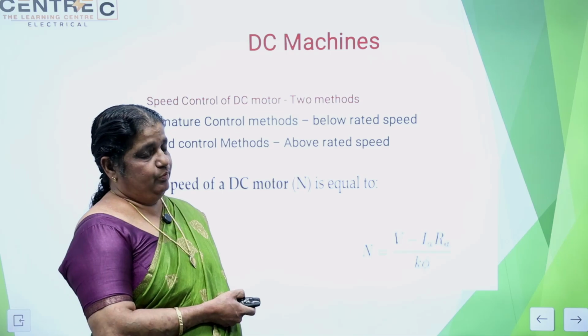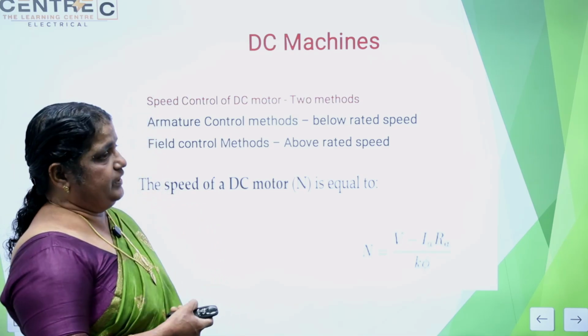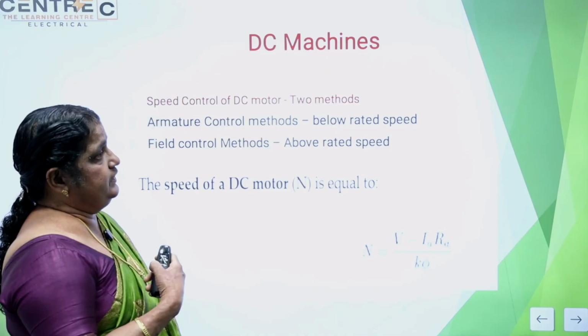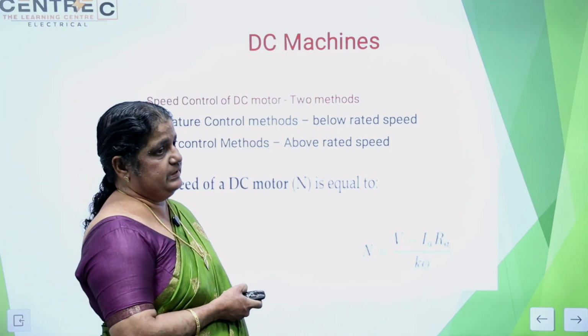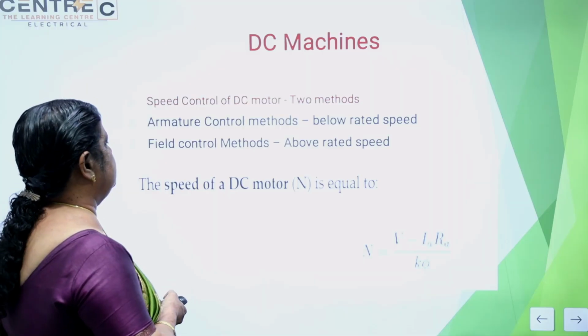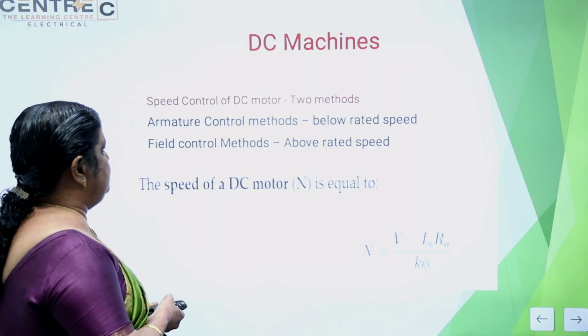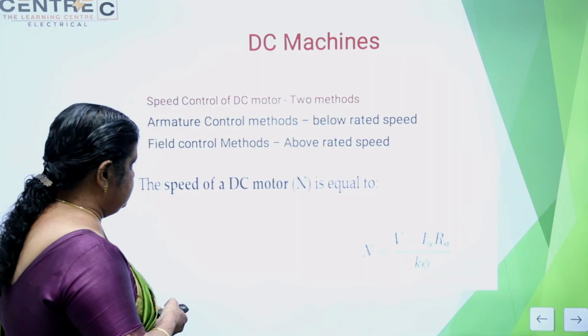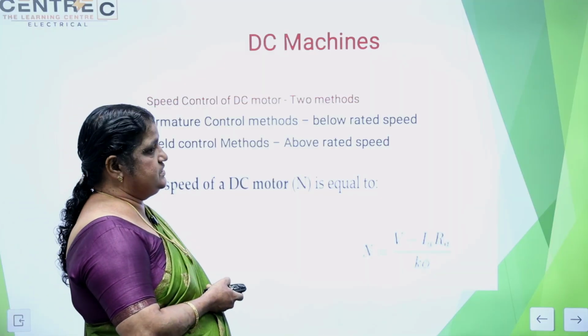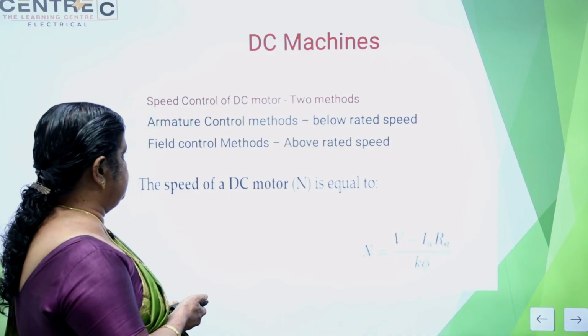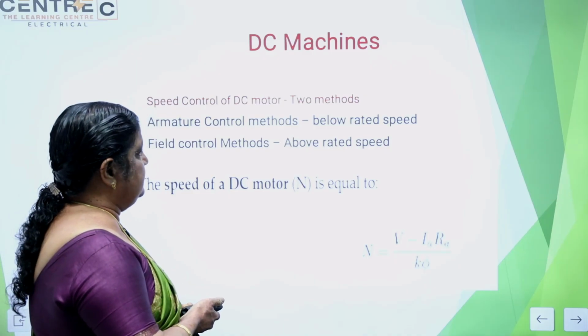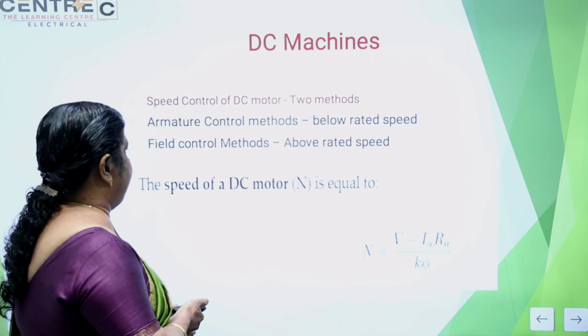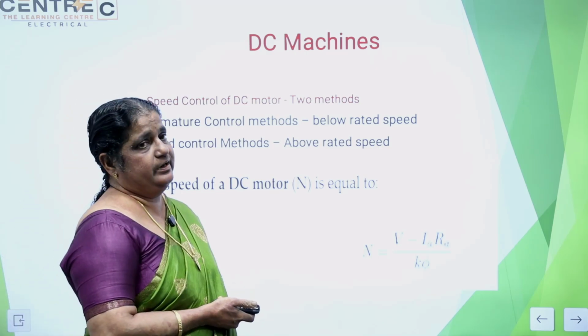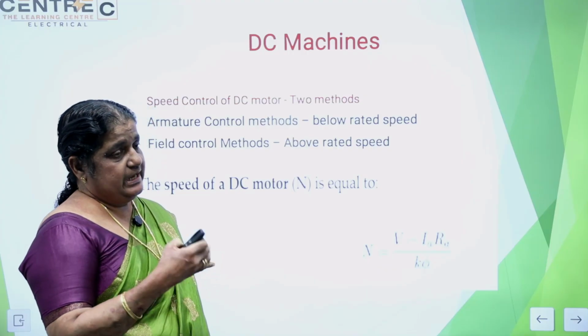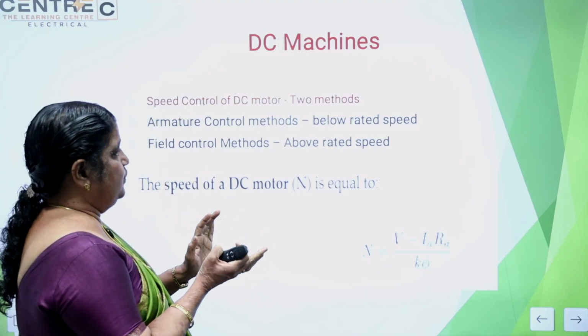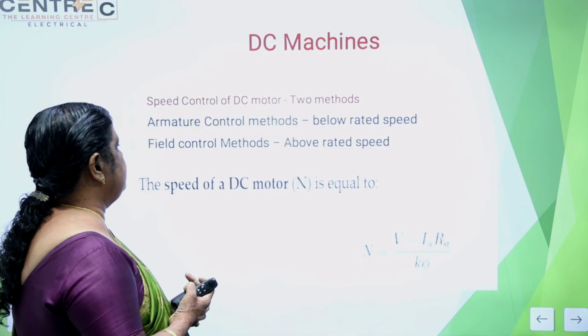Nowadays, DC machines are used for different industrial applications. For different applications, the speed of the motor is variable. So for getting variable speed, we can use different control methods. Mainly two control methods, depending upon the function: armature control and field control. The two important parts of the machine are the field and the armature. When the speed of the motor is above the rated speed, we can use the field control method.